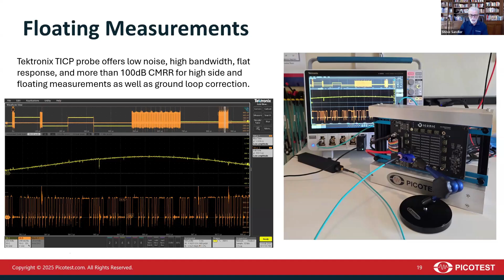There are also accuracy concerns, and this is one that I had never really considered before. I'm not sure why, other than I don't think anybody questioned it. But using the same demo pattern that I showed before, in order to try to keep this focused, we used a single demo board running a single demo pattern. We used one oscilloscope and we used the same channel of the oscilloscope for every measurement. So we removed an awful lot of the tolerance uncertainties by using the same scope and the same channel and the same demo board and the same load controller. We even measured on the same test point, but we measured that voltage response with a bunch of different probes.